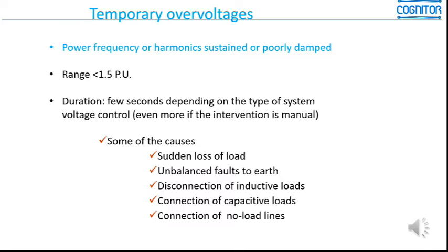Some of the causes of the temporary overvoltage are the sudden loss of load, we'll show this in the next slide, some unbalanced faults to earth, the disconnection of inductive loads, and the connection or disconnection of capacitive loads also. And we will give some examples in the next slides.